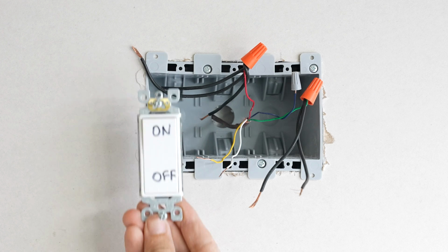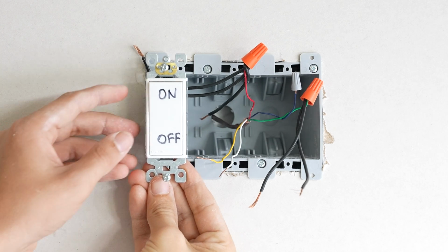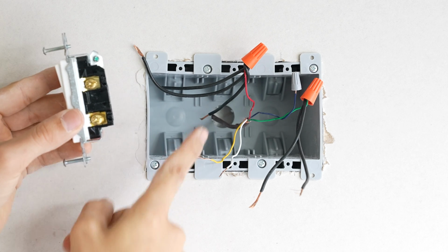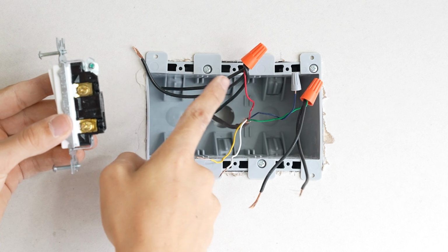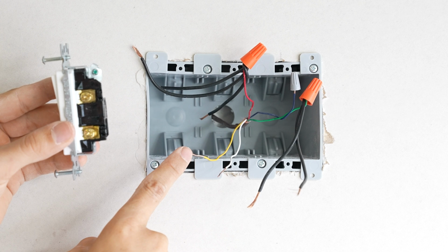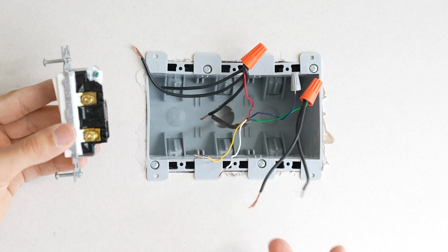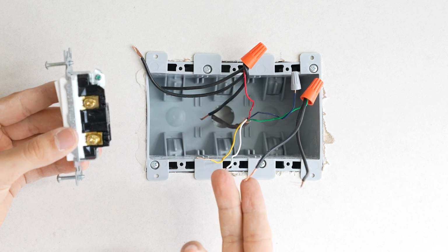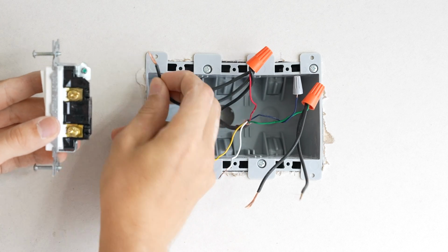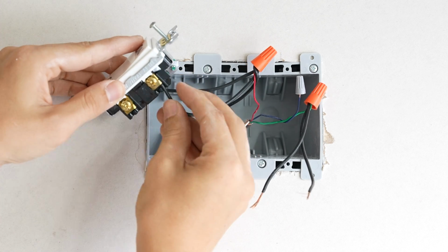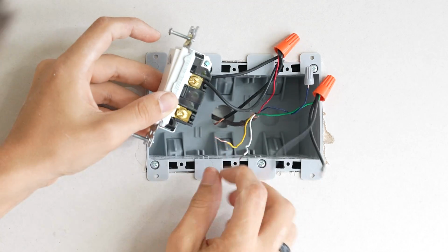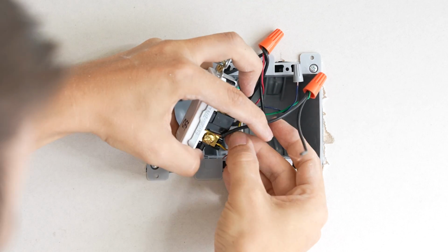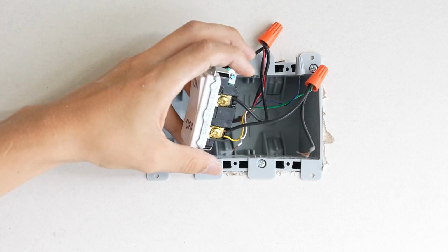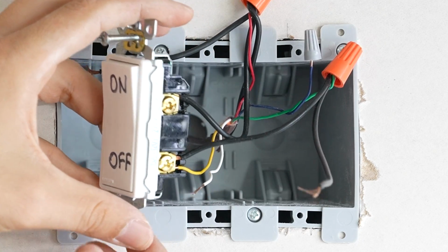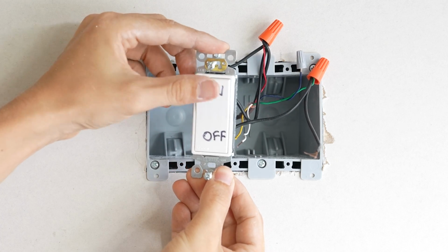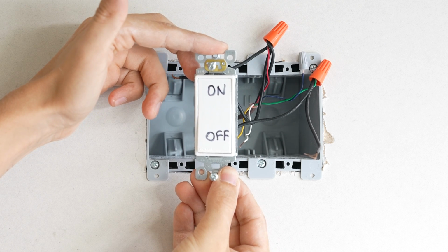Now that the pigtails are done, I can proceed to wire up the switches. I'll start with the air conditioner switch first. I put one of the red wire pigtails into the top terminal, which will be my power coming in, and the bottom terminal is going to need the yellow wire, which is for the cooling, and one of the green wire pigtails for the indoor fan.